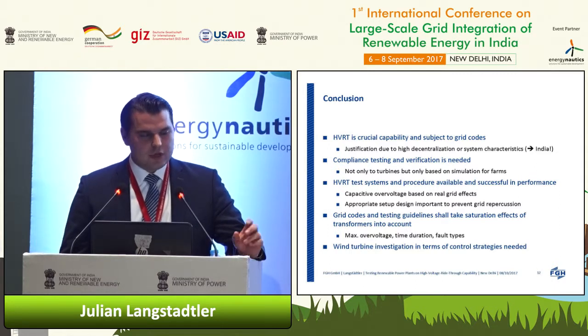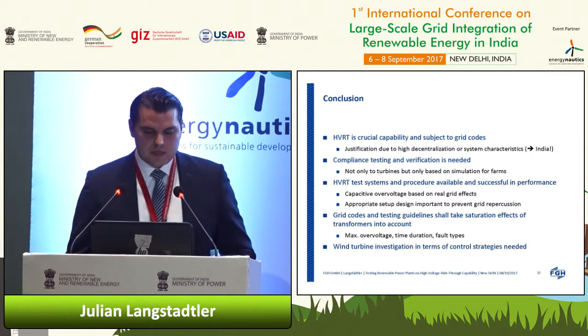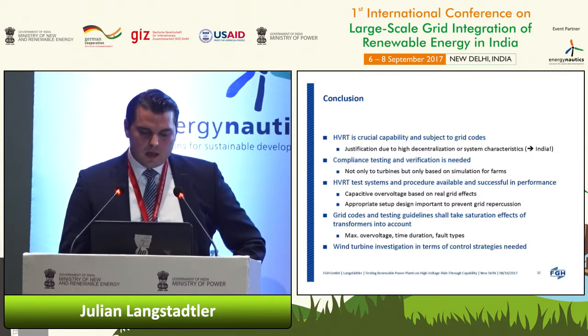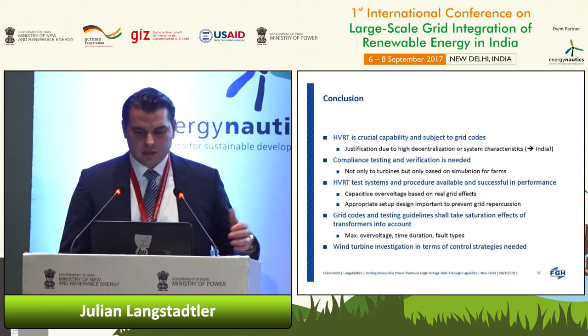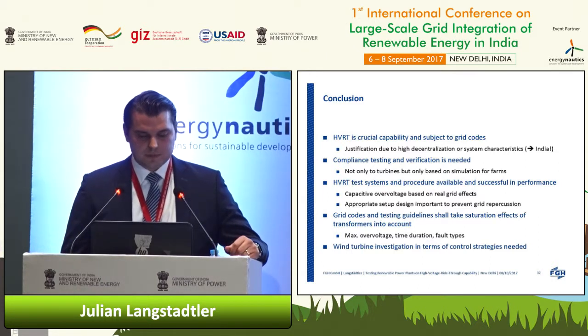We already heard that compliance testing and verification is needed, and HVRT test systems and procedures are already available and successfully in operation. We have a few of them already manufactured, and they are successful in operation. We stick to the capacitive overvoltage configuration since it's based on real grid effects. There are also other concepts where you use transformers. However, we do think that the system effects are better simulated with capacitive overvoltage. An appropriate setup is also important for the prevention of grid repercussions, meaning no resonance with harmonics or anything else.